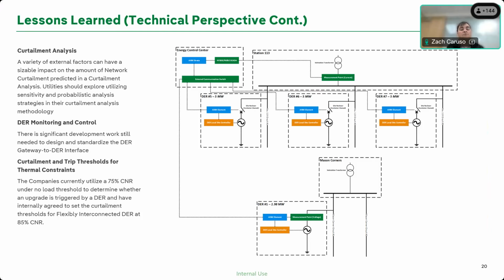There were some significant challenges when we were connecting these sites having to do with the DER gateway, which is our piece of equipment at the site that is the local controller for us. It's able to trip the customer offline at the recloser, like I mentioned, and it's what's passing these limits to that PV site. And we had a significant challenge with getting that to work consistently and reliably, because there's not really standards. There's not really a great understanding of what is needed to accomplish this, at least at the time that we were implementing this within that community.